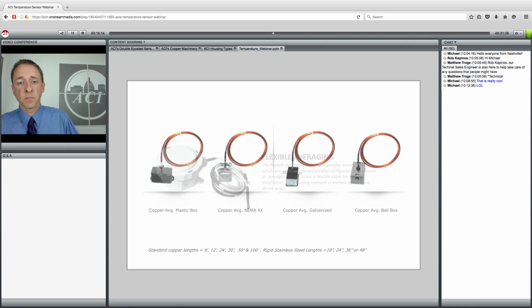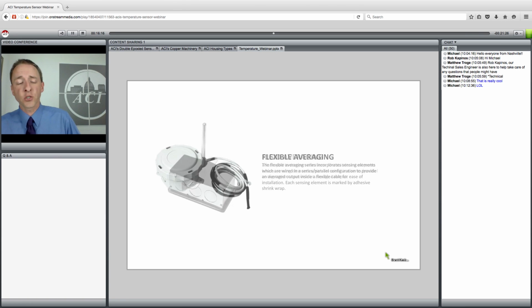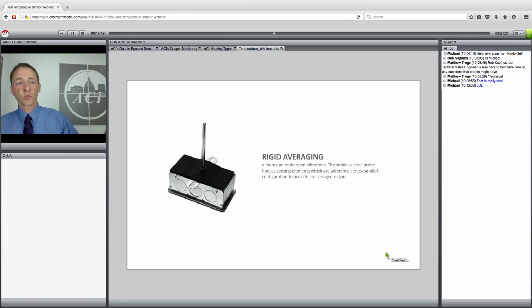We have also the ability to do what we call a rigid averaging sensor, which is going to look real similar to the duct style sensor that you see here, but it's going to have a longer probe, 18, 24, 36, or even 48 inches in length, and then have multiple sensors along the length of that probe to get you an average of those multiple sensors. And so that works well in even tighter spaces where you may not have the space or the room to stretch out an 8 or 12 or 24 foot bendable averaging sensor. You can use a straight rigid probe in that place as well.